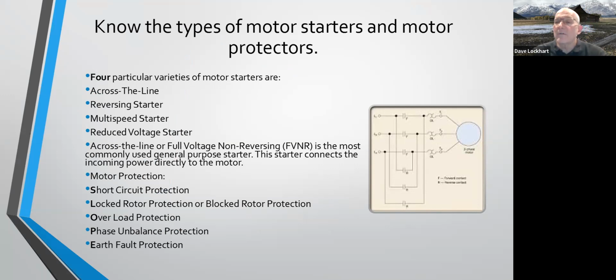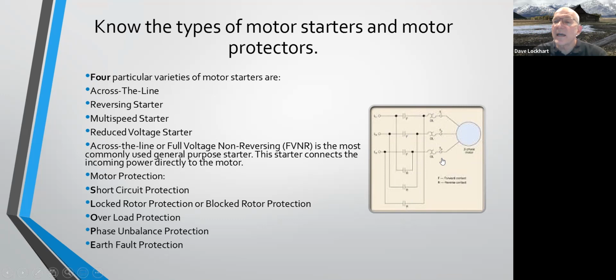So over here on the right is a very simple diagram showing your starter for your 3-phase motor. So you've got your contacts across here, you've got your overloads, and then you got your connection to your motor. So pretty straightforward. Motors are going to have those just to help get them started. The contacts for those starters are higher amperage. They allow a larger load to serve the motors versus having a switch or something else out there. So that's usually why we use motor starters.